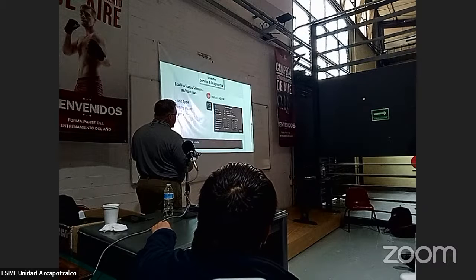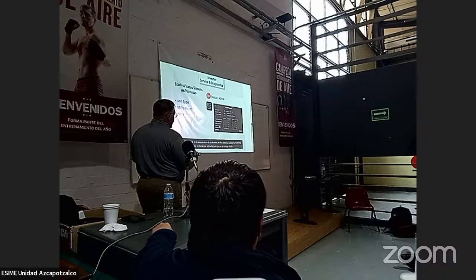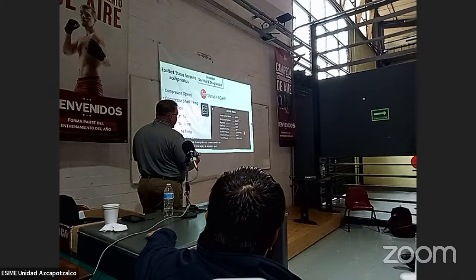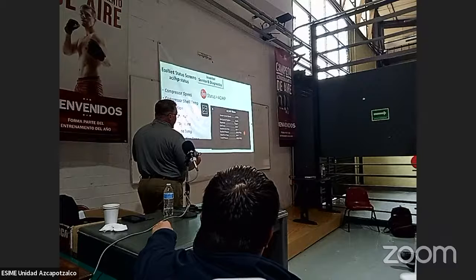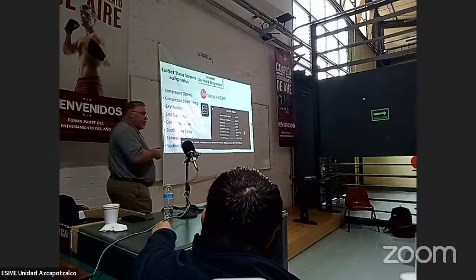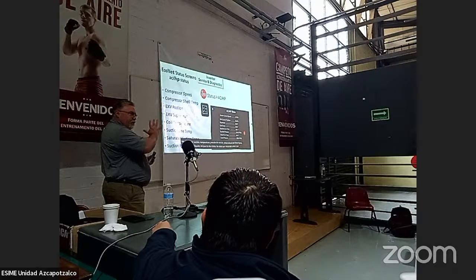So you can also do a status screen. On these status screens, this is what will come up first. You can see what you've got. It's a variable speed 2-ton. It tells you what your outside air temperature is, what your coil temperature is, and how it's operating, depending on if you energize it or if you select it. Then you can look here and it'll show you what the inverter current speed is, how many RPMs your compressor is turning, what your EXV current position is, what your superheat is, your suction line temperature, suction pressure, liquid line temperature, liquid line pressure. So it tells you all the things you need to know that's going on with the system right from the EcoNet.